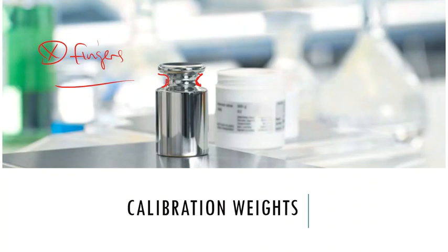And all of that will transfer mass onto a calibration weight. And we cannot have mass transferred onto a calibration weight, because then we think that the balance is off, and it's not. It's just that you're a filthy animal and you have contaminated something that we need to be using in a laboratory that has to stay clean. So the reason those divots are at the top is that very often we take a pair of tweezers and use them to pick these calibration weights up, set them down onto the balance, record the masses, then take the same pair of tweezers and grab that calibration weight back off of the balance pan and carefully set it back into the case that it comes in. All right, so that's the proper way to handle them.